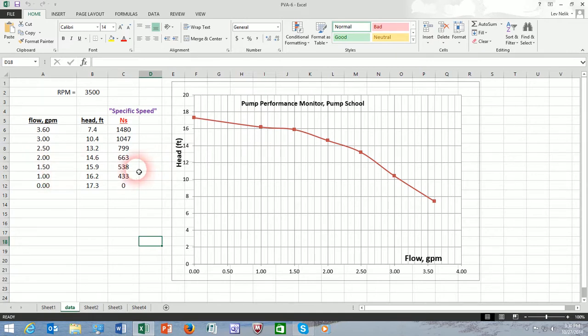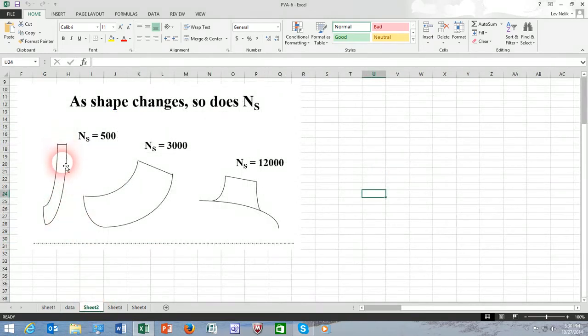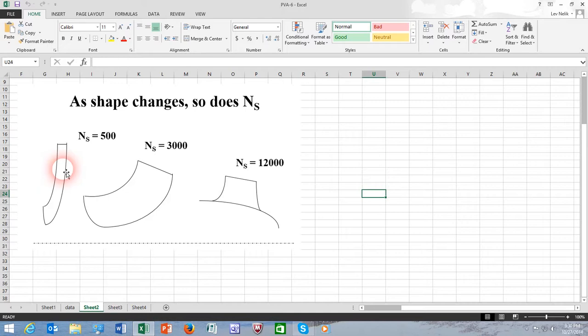So which point should it be? If we choose the one or one and a half gallons a minute, the specific speed is nearly 500, which will indicate the shape of the impeller being something like this: very narrow, skinny impeller, characteristic of very low flow and high head applications. Examples: boiler feed pumps, multi-stage units.